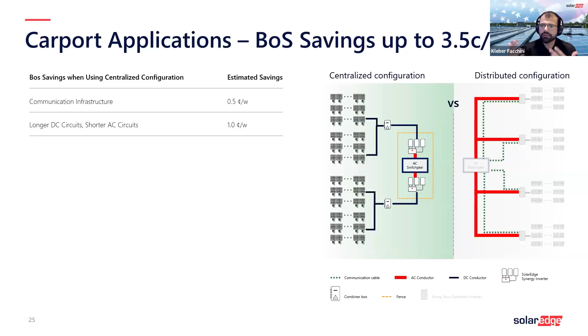You have longer DC cables or longer DC circuits instead of AC, with a short AC circuit. Because we're running aluminum cables and running two cables on average - positive and negative - instead of three for each phase on the AC side, we save about a cent a watt.